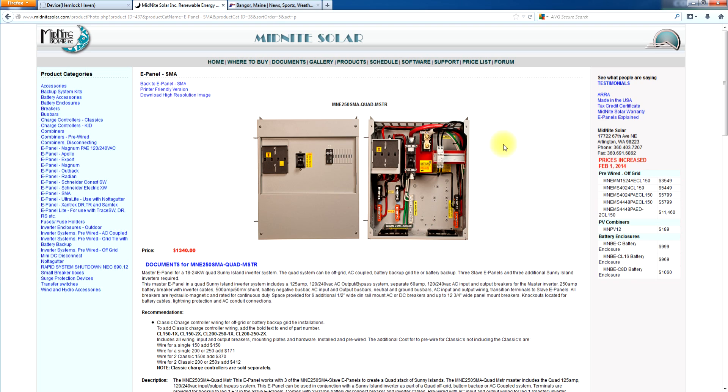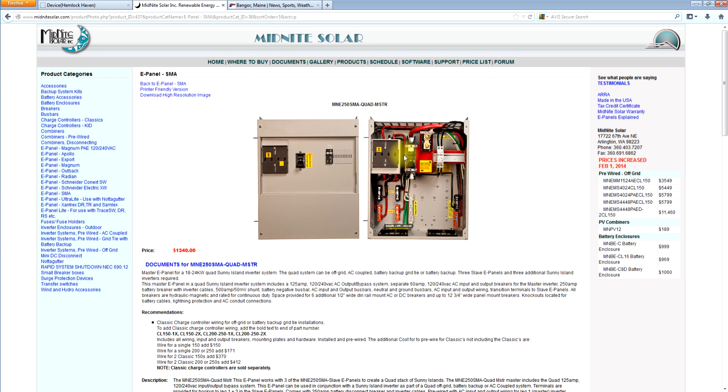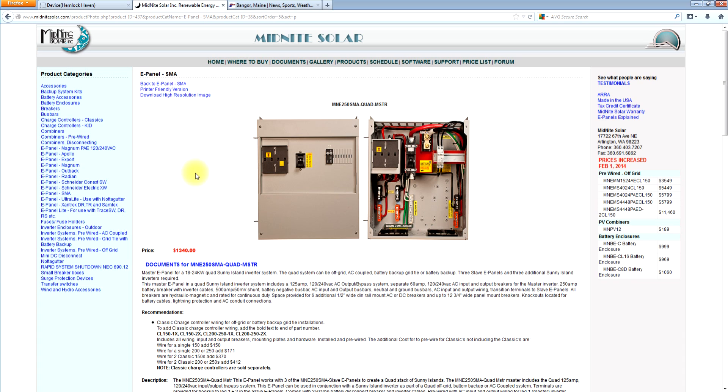I'll show you the combiner box in a little bit. But as I say here, we've got the bypass which bypasses all four Sunny Islands at the same time and connects the grid to the critical loads or generator if it's off grid. And you've got your run breakers over here for the Sunny Island, input and output breakers. And then you've got your bus bars and your transition bus bars. So basically this would be for doing four Sunny Islands, and you would need three slave e-panels.